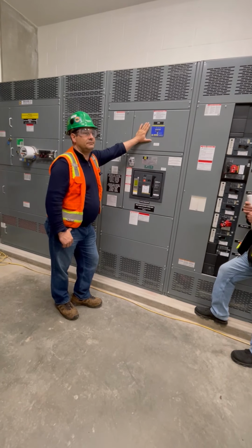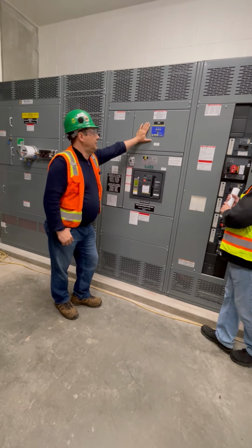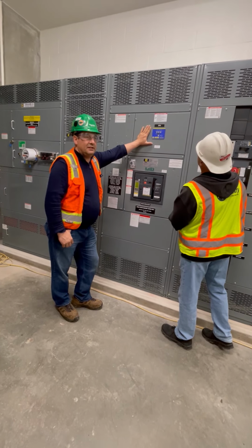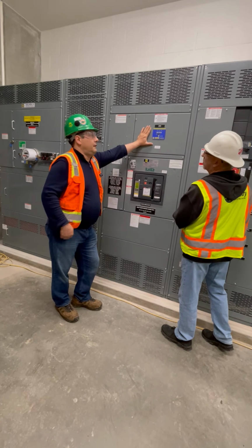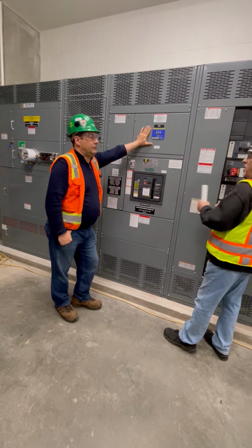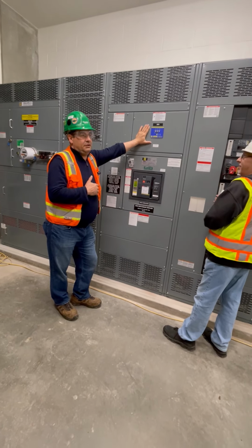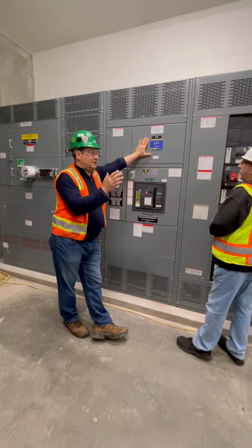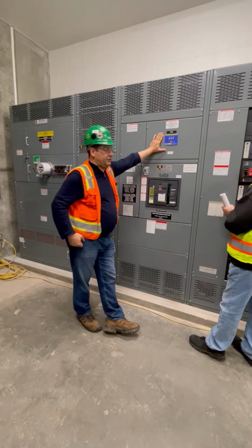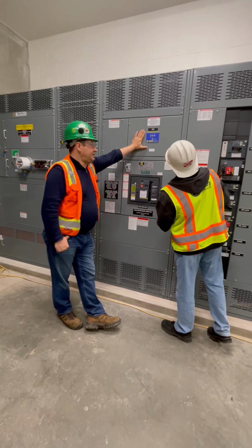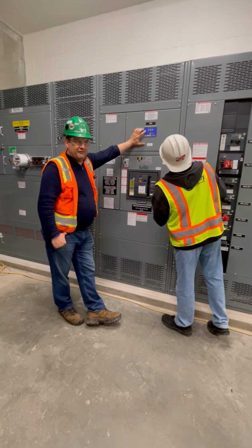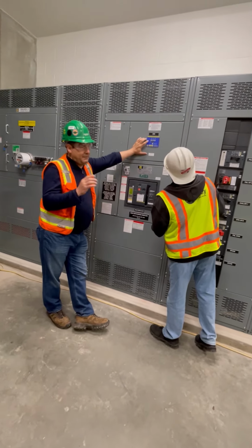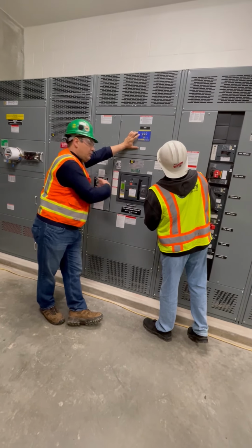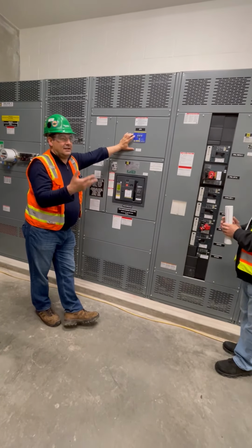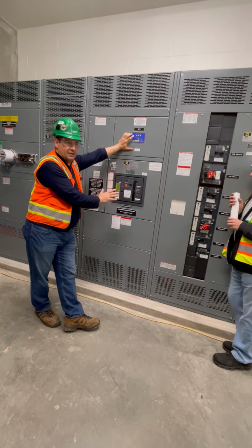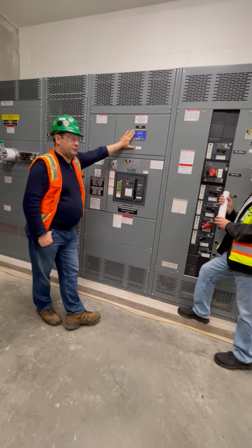5-year warranty on them. The only downside to that is you have to call in every time, and you have to wait until they ship you one. So, having one or two on hand might be a good idea. I always recommend it. Yes, they have longer warranties than standard on a switchboard. The standard warranty on a switchboard is 18 months. These are the only product we carry that I think have a 5-year warranty. Unless, and I mentioned that just in passing, if we would have done startup on this, we normally add another year or two of warranty on top of the standard warranty. But this only includes product, it doesn't include labor.